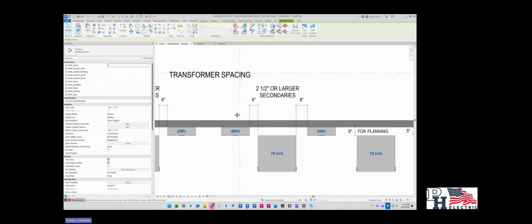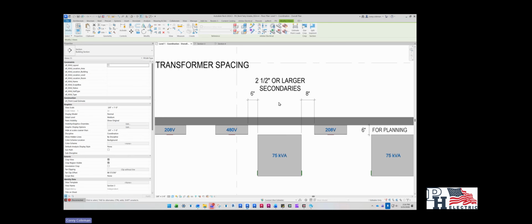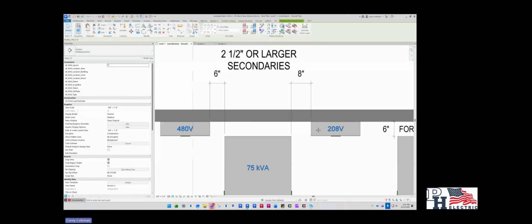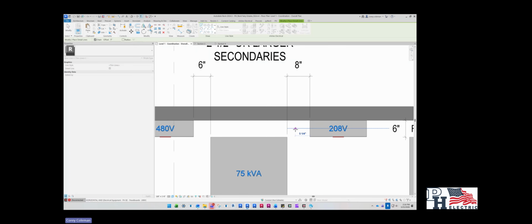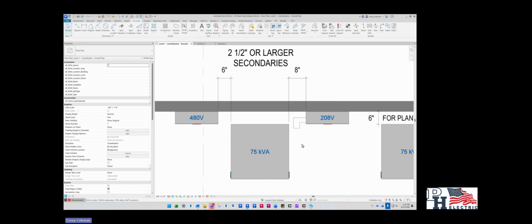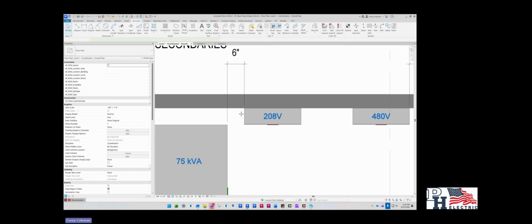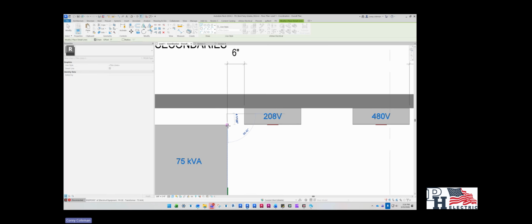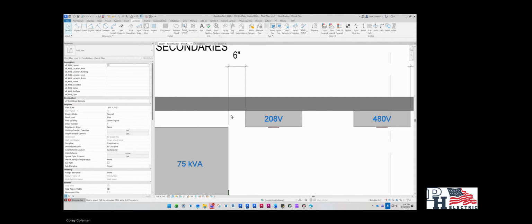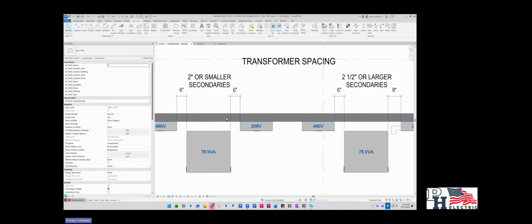However, when you're dealing with larger secondaries, such as I think it's 400 amp or over, you want to deal 2.5-inch or larger secondaries. You want to increase your spacing from your 208 panel and your transformer to 8 inches. The reason why is this allows you to use those larger 3-inch connectors. That'll probably bump out to about 6 inches here when all is said and done, and give you a nice straight path to your transformer here. If you did that over here with the 6-inch one, you're going to be probably running up to the backside of the transformer here, and it's going to be a lot harder to get that connector in.